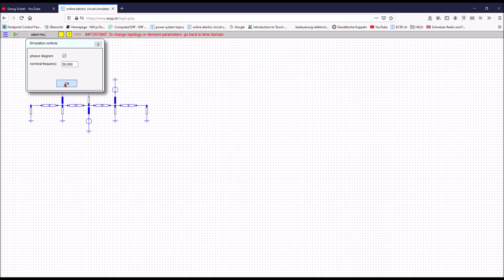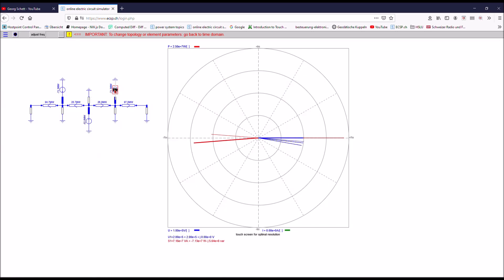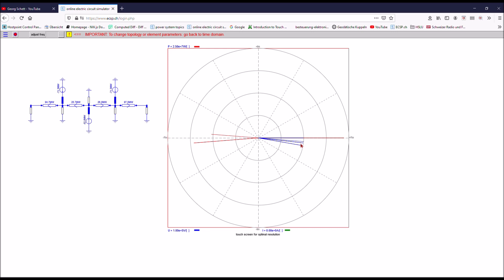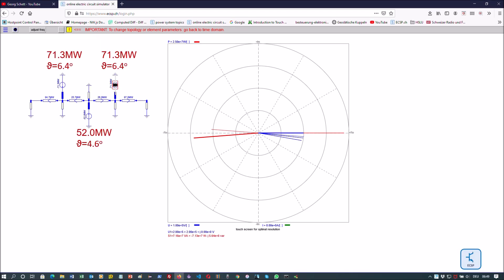Let's now move to the phasor domain. Here are the phasors — you see the phasor for the induced voltage of the first generator, this is the arrow you can see here. Then we have the terminal voltage, which is what connects to the line, and in between you have the rotor angle, which is about six degrees and delivers 71 megawatt. You can do the same for all the other generators — this is the induced voltage of generator number two and you have the terminal voltage; in between you have the phase angle. You can also see the power output of the first generator: the values and the angle between the real power and the reactive power. Here are now the power outputs of the generators with the individual rotor angles.